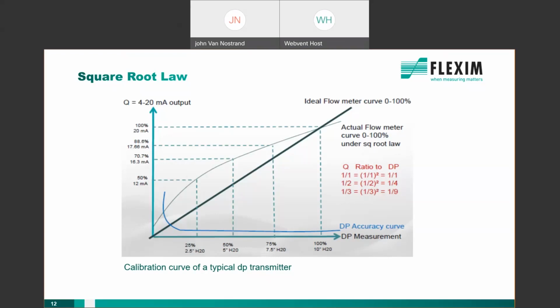At 50% of the flow range, the DP is 1/4 of the span. So you see that 1/2 squared equals 1/4 of the DP. And then at 33% of the range, the DP is 1/9 of the transmitter span. This is the effect of the square root law. And this is why the orifice plate only has a turn down of 4-to-1. And believe me, 4-to-1 can be pushing it. It's really closer around 3-to-1 once you consider vibration, process noise, and transmitter dampening. It's nearly impossible for the transmitter to measure below 25% of the span while using the square root extraction mode. This is why many applications have 2 transmitters stacked, and they span one transmitter for the very low range and then get a fresh start when the square root law gets into those low flow conditions.